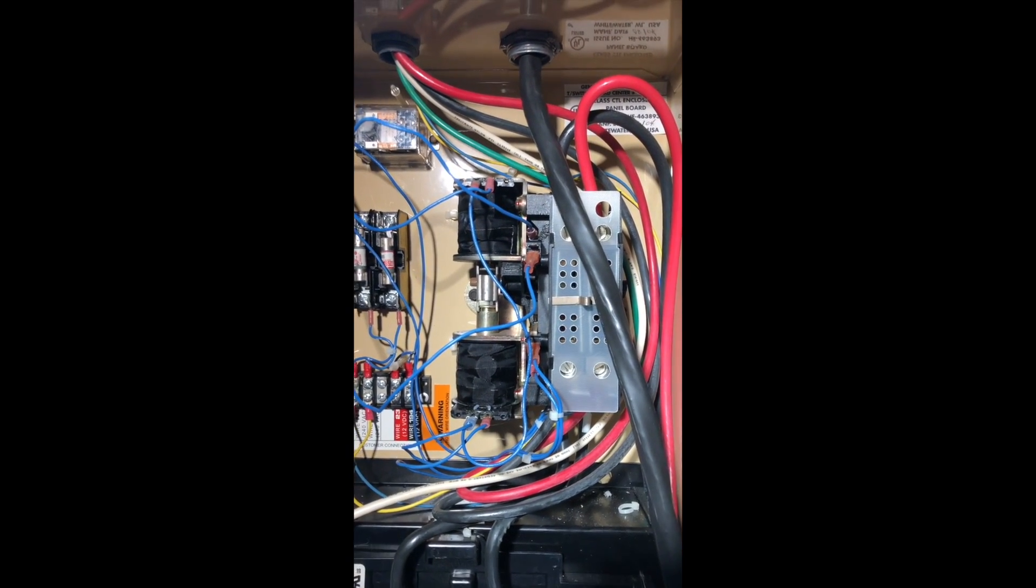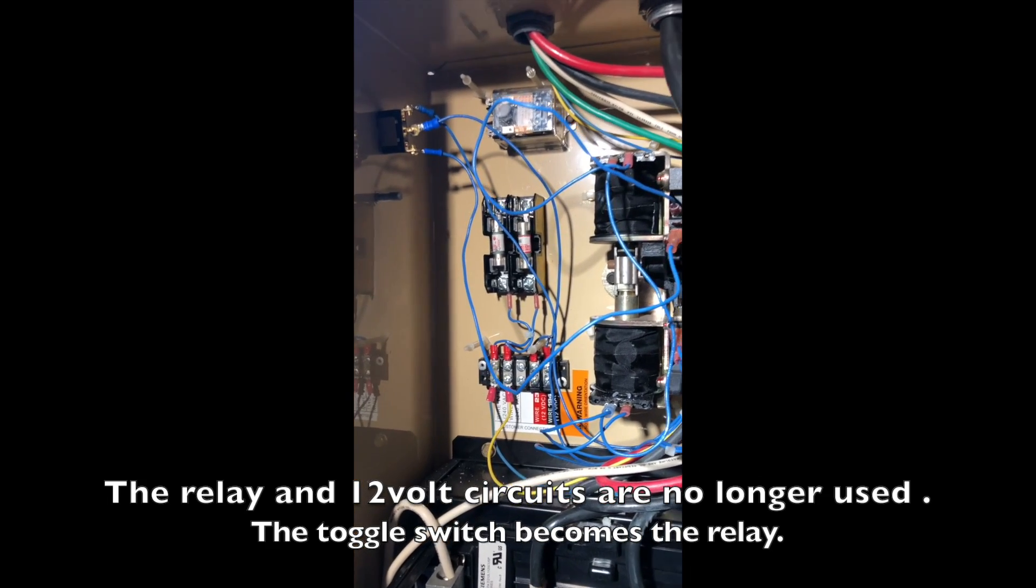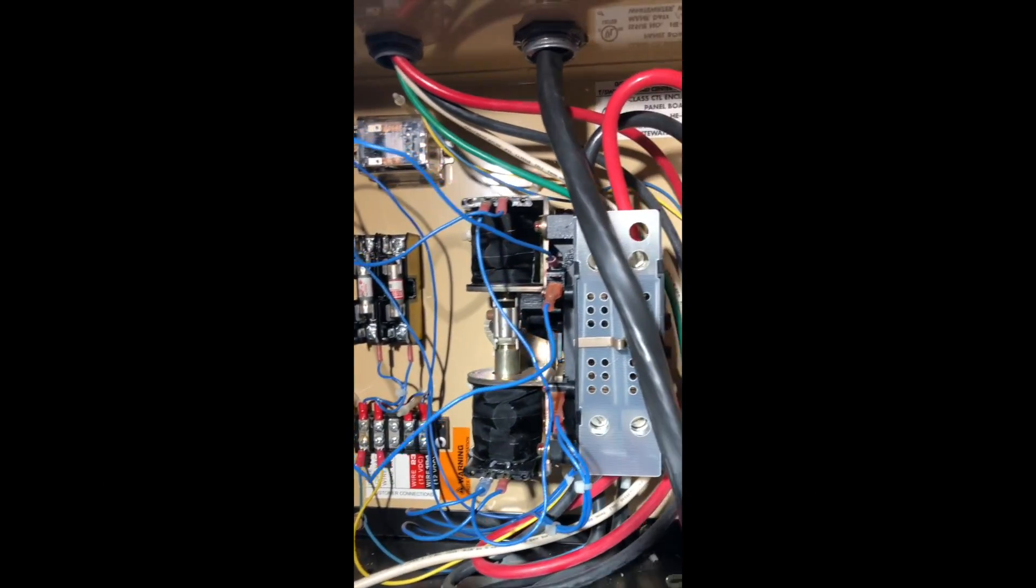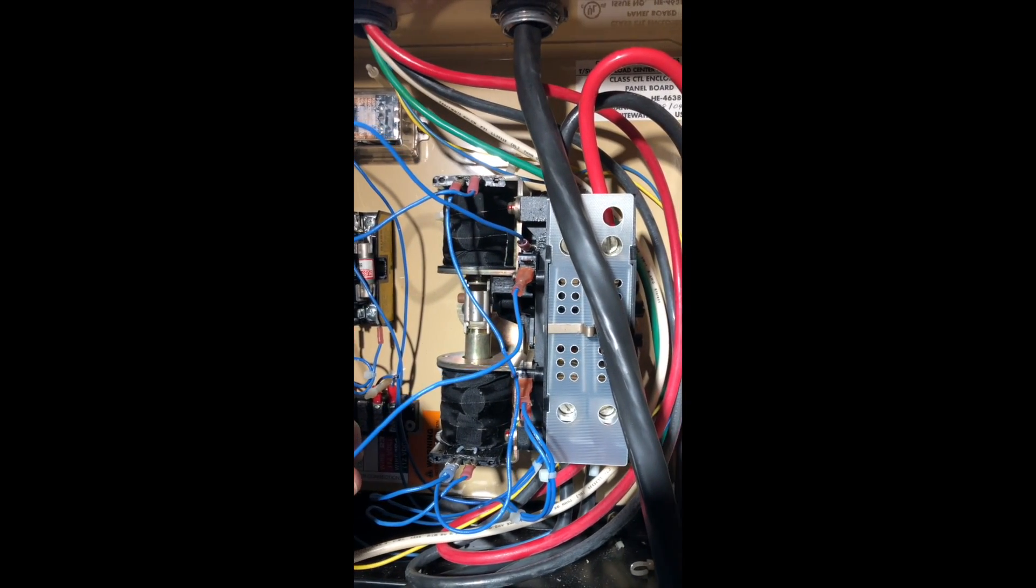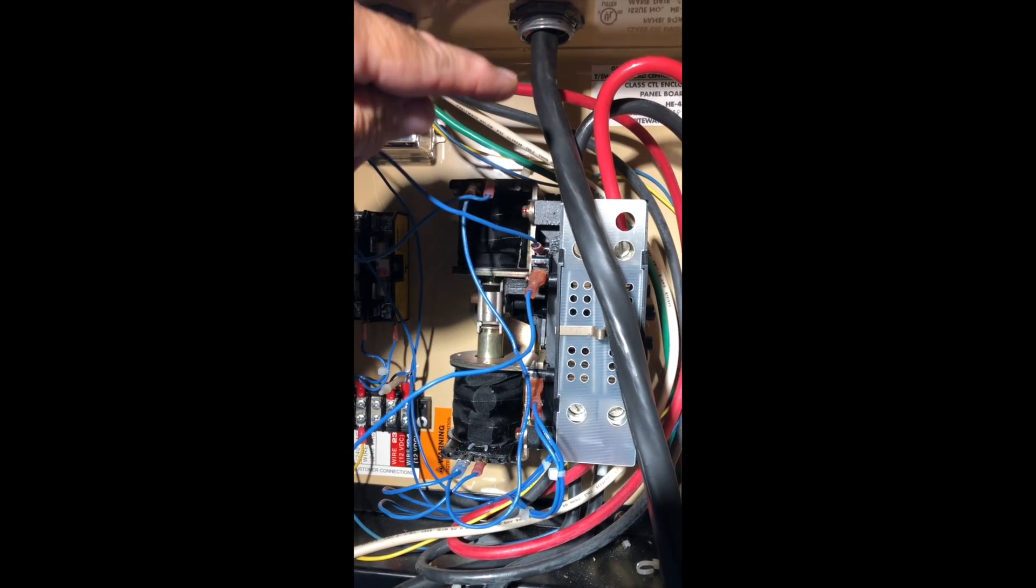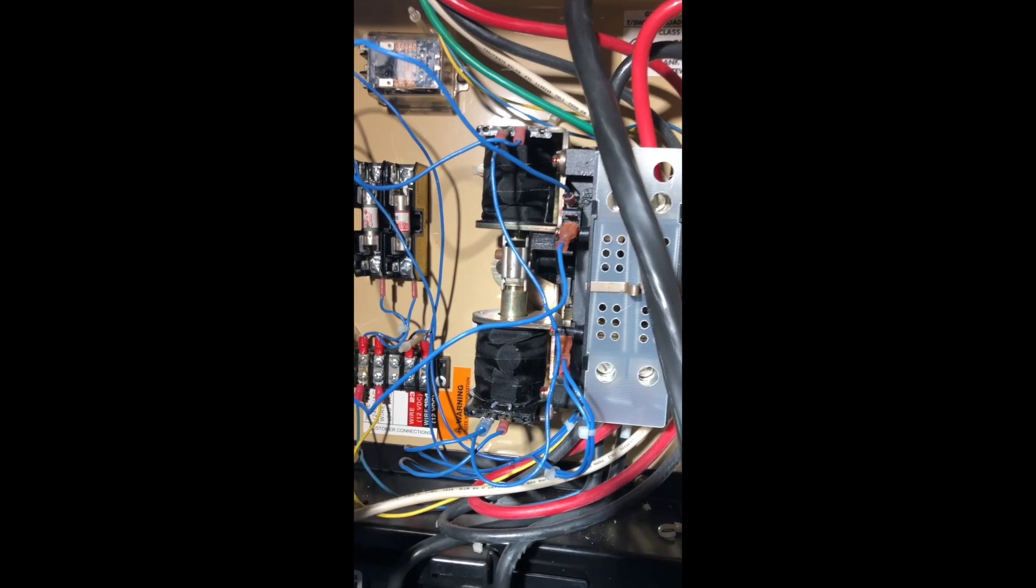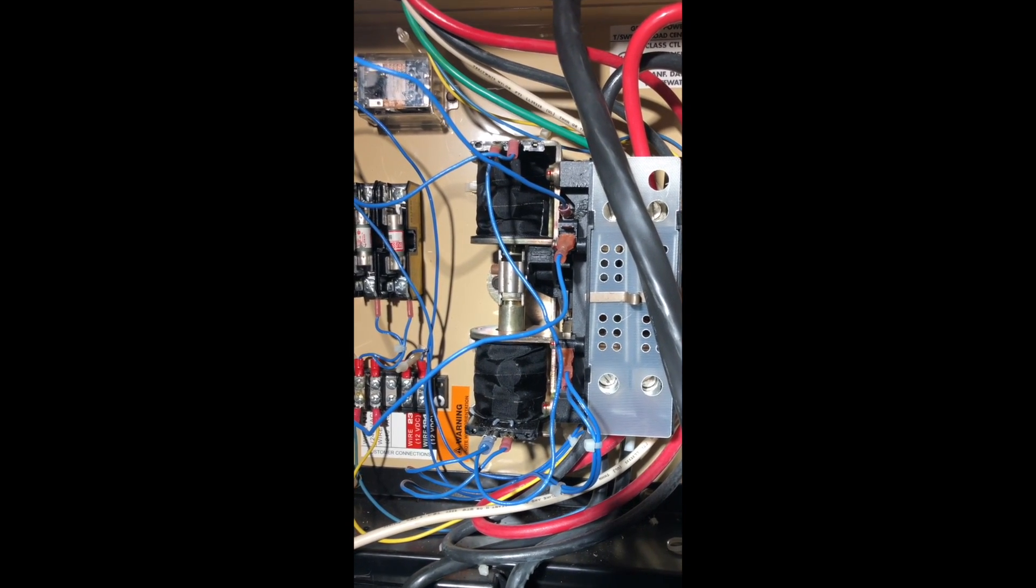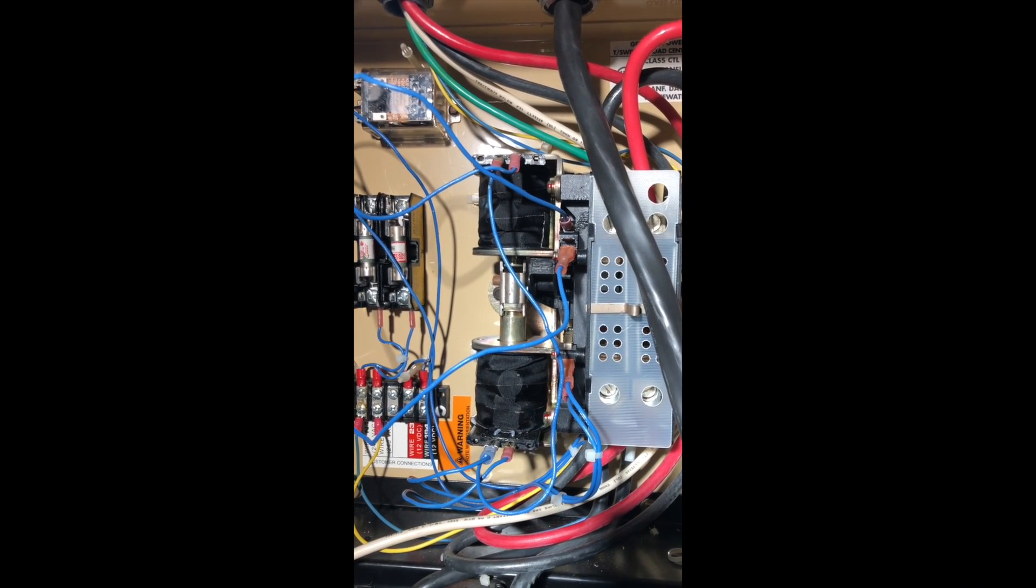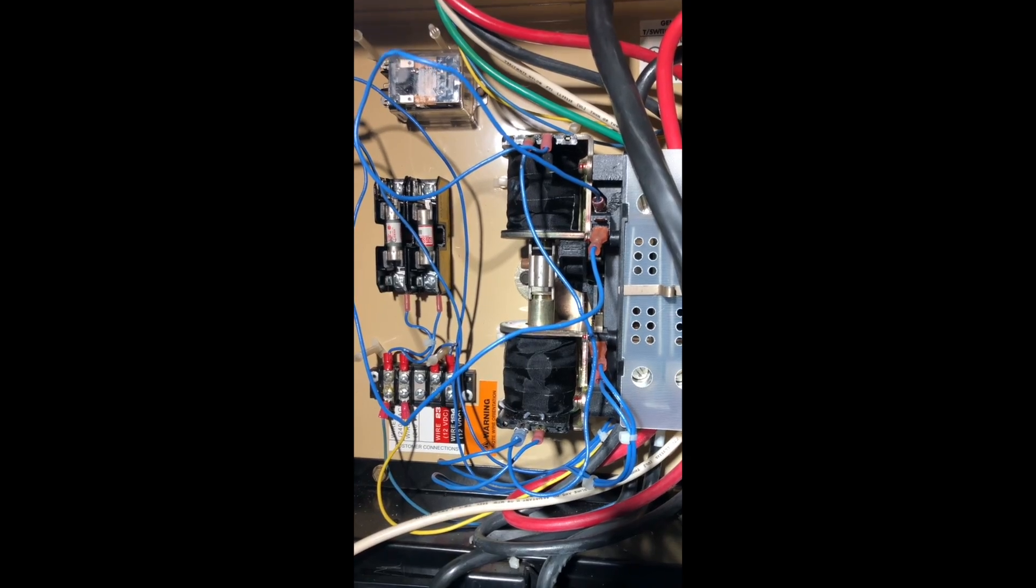All I did was put a toggle switch right here, and this toggle switch is now going to be my manual transfer switch right here. I haven't labeled it yet, but I will. One thing of note is the way this was previously wired from the factory. The top of the transfer switch got power from the utility side, and the bottom of the switch got the power from the generator side, which makes sense because this was supposed to be automatic. That function is no longer possible with the way I have this set up. I just wanted something very simple because I no longer have an automatic whole house unit.